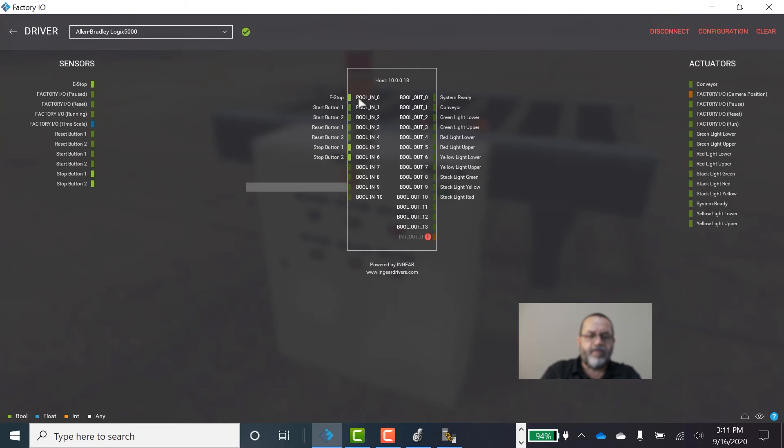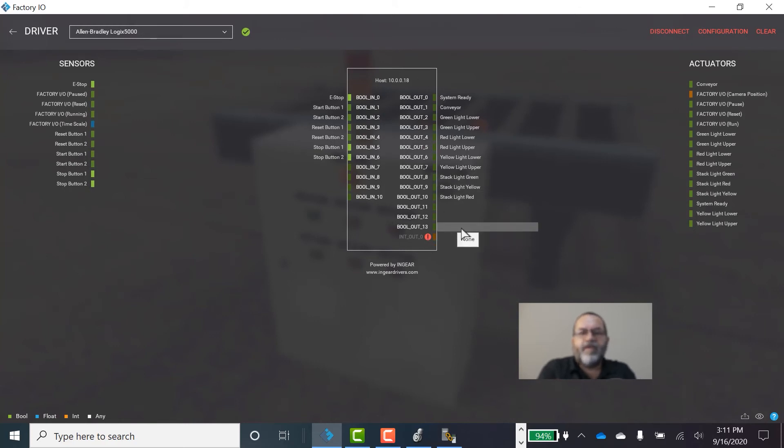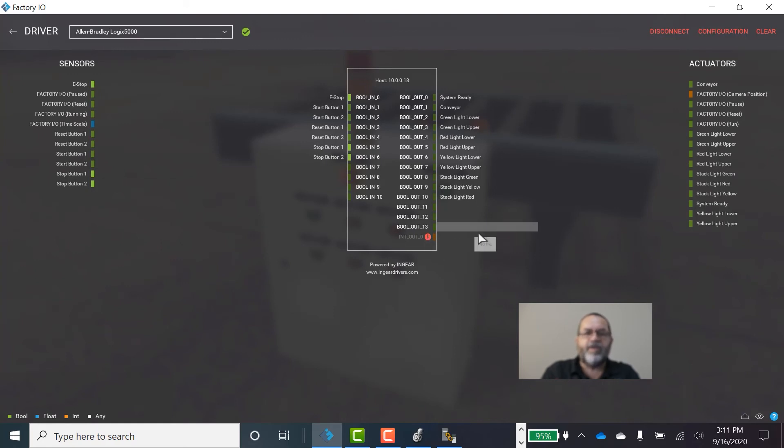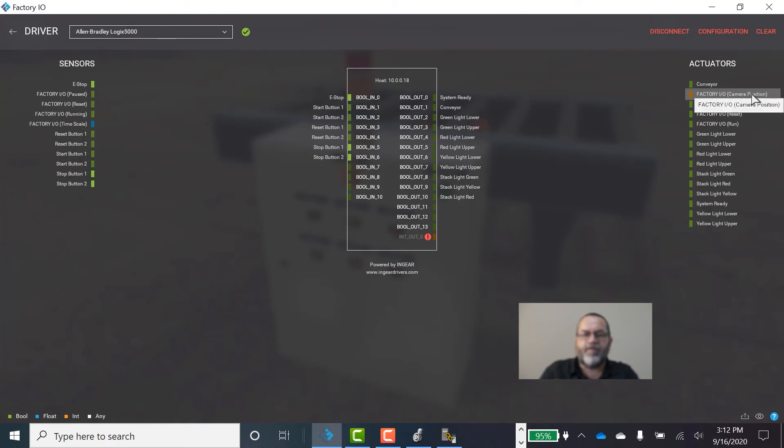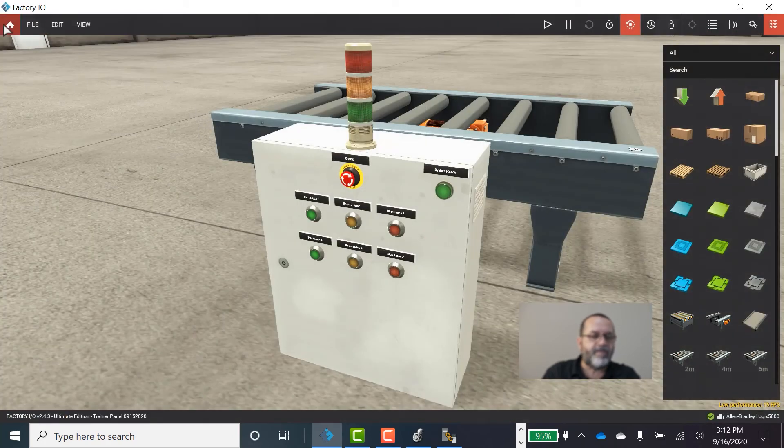And you maybe saw this all flash. Maybe I'll disconnect and reconnect it again. Watch all these indicator lights here. Hit my Connect. You notice they all went red. And then they all, except for this guy, went green. That means initially it didn't see the IO tags. And then it updated. And it found them. And it said it's happy. It didn't find this integer out zero. So I've got a red flag there. But I'm not using that. That's for, if you want to know the camera position. It's an analog output. And I'm not using it. So I've got a flag there. I don't care. And I'm online. So now I'm going to go back to my scene.